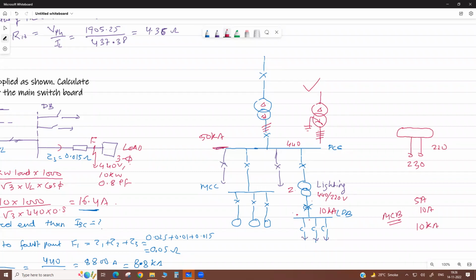Means in lighting circuit, hello, this transformer. See, if you check here the fault level, then the impedance of this transformer, impedance of this cable, impedance of this cable, impedance of this transformer also, then fault level here is reduced. If your lighting circuit fault level is reduced, it means your cost of switchgear is reduced, mainly due to the fault withstand.